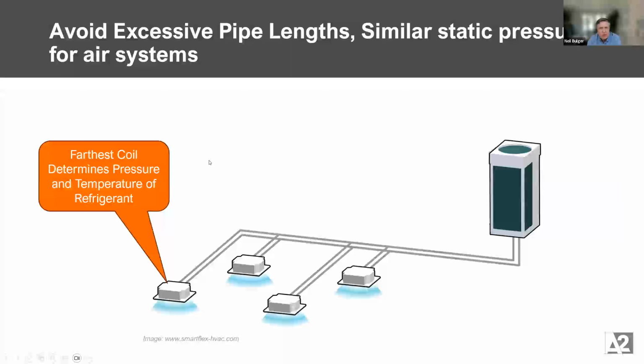Okay, so some other key things, thinking about how to lay out VRF systems and what can drive efficiency. And these next ones I'll touch on don't really show up in the modeling per se. It's more just what can drive overall efficiency. And there are some inputs in the software, but it's more just best practices. So pipe length, excessive pipe length. Some of these products, they say you could run 300 feet. It's really good to think about pipe length, kind of like you would think about static pressure in an air duct system. And you don't want one run that's so long compared to all the other ones.